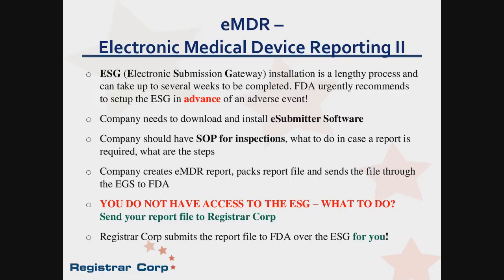Here we have more about eMDR. It is a very lengthy process, and like I said earlier, you only have 30 days, and just setting up the gateway can take a long time. You also have to have software called eSubmitter, and you must go through the process of submitting a lot of data into the eSubmitter, and all of this takes time. We are here to assist you with this. All we ask is that you send us the file so that we can submit it to the FDA. The FDA says that the file must be a certain way, so we will assist you all the way through.